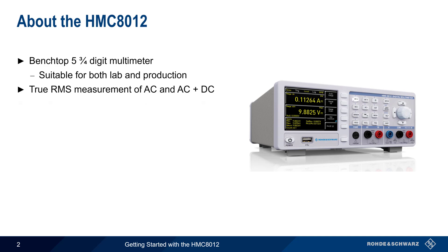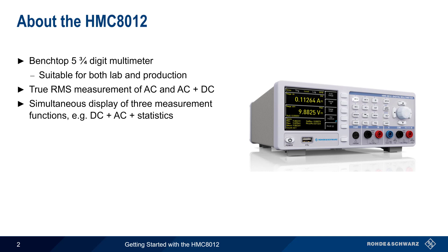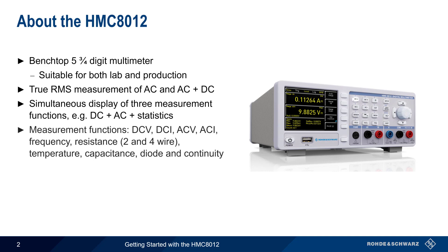It can display up to three measurement functions simultaneously – for example, DC, AC, and statistics. The main measurement functions of the HMC include DC and AC voltage and current, frequency, 2 and 4-wire resistance, temperature, and capacitance, as well as diode and continuity testing. Results are presented numerically with common statistical values, and special measurements such as limit testing, DC power, and dB or dBm values are also supported.